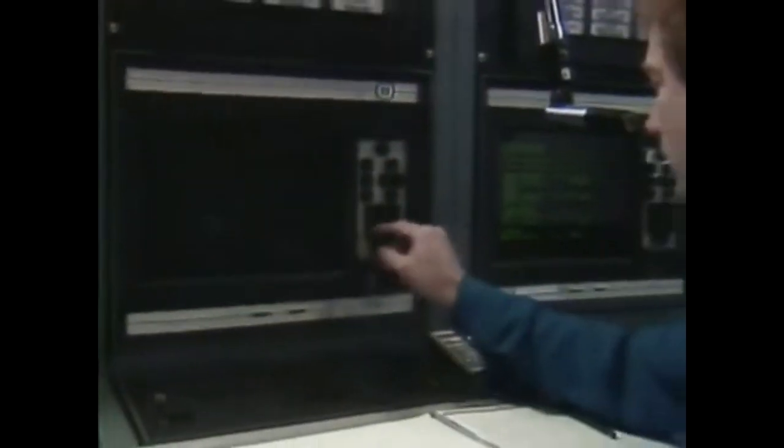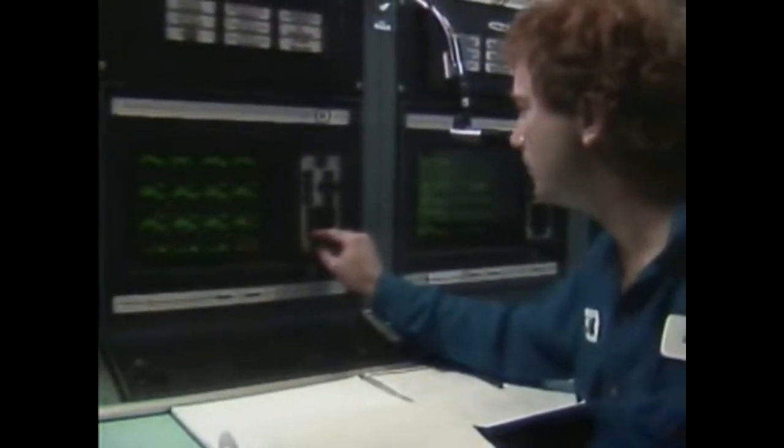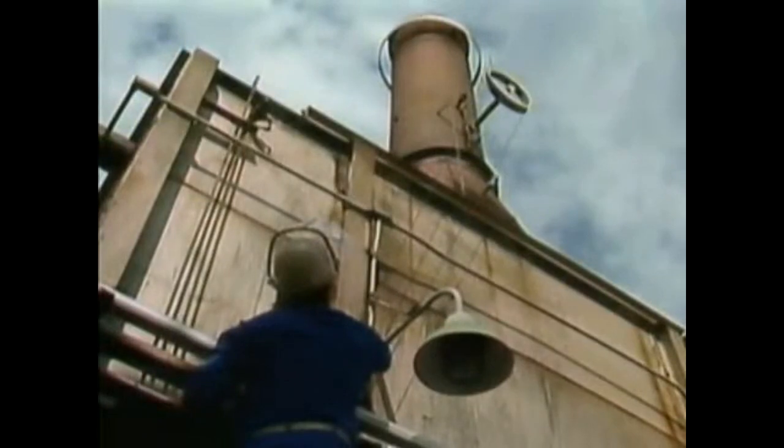To correct this problem, first you may need to take manual control of the furnace and start cutting back on the fuel flow to the burners. When the fuel flow is reduced, the haze in the firebox should start to go away. Then the stack damper and the burner registers can be adjusted in small increments to meet the desired draft and excess air targets. A sudden rush of air into an air-starved furnace could cause an explosion, since there may be unburned fuel in a hot environment.